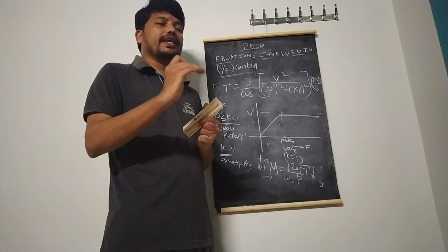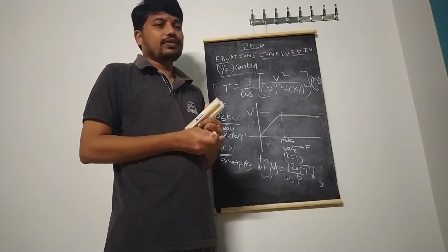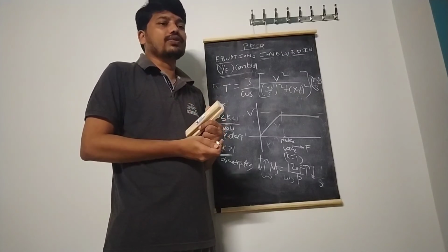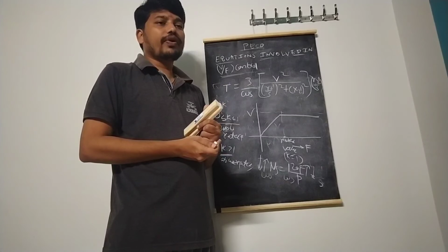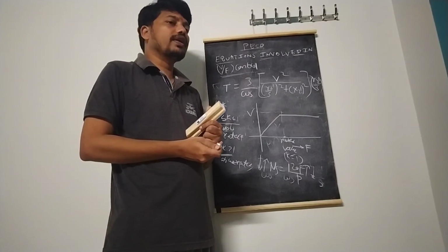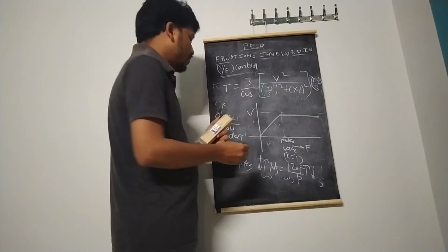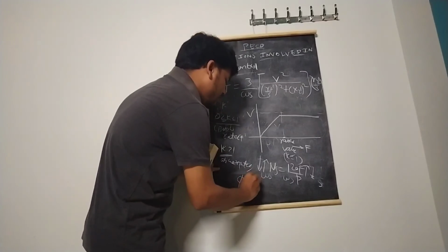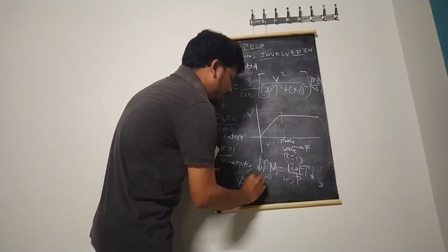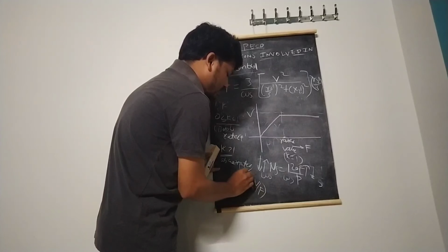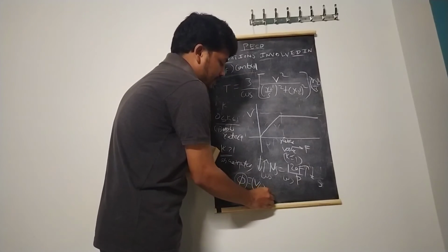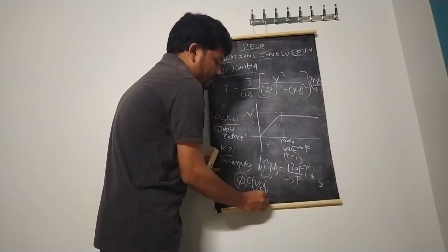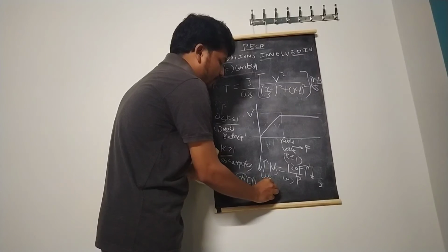So definitely k should be 0.5. Here, if k is 1, it is 50 Hz; if k is 0.5, it is 25 Hz. So definitely the voltage also has to change proportionally, because our aim in any technique in the induction motor is to maintain the flux constant: while decreasing the frequency, we should decrease the voltage, and while increasing the frequency, we should increase the voltage.